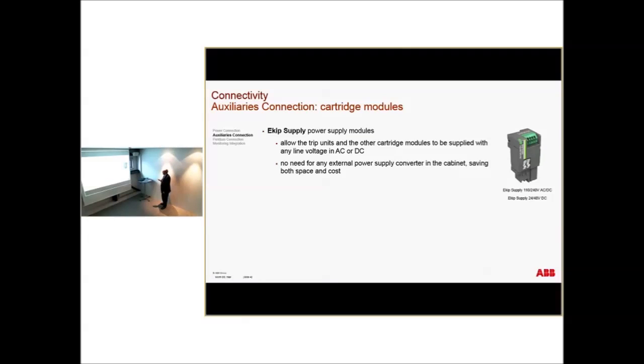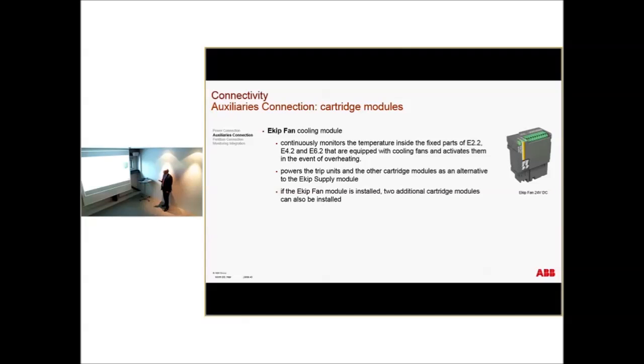Again, here is the Ekip Supply that I explained before. You can have 110 to 240 volts AC or DC, or 24 volts, 48 volts DC. So you don't need an external supply converter and cabling, saving cost and space. This is important. The Ekip Fan, I mentioned before, can control up to 3 fans. It's the breaker itself that decides when to activate, according to the programming you made inside the breaker.